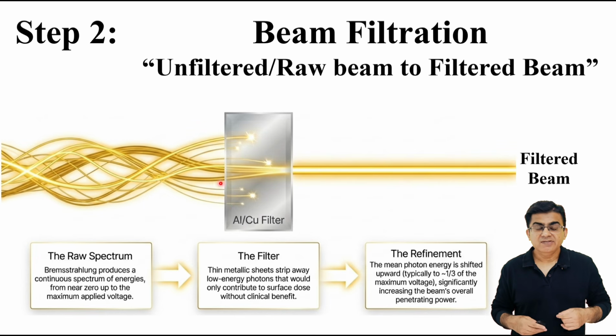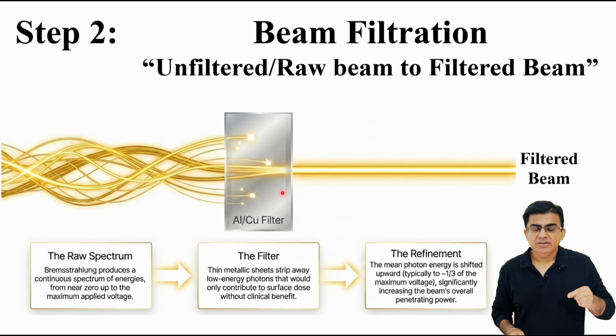It acts as a ruthless physical barrier. It selectively absorbs those dangerous low energy photons. This physical filtration process is called beam hardening. Beam hardening. Remember, examiners will strictly look for the exact textbook terms for this process. Beam hardening. By stripping away the weak photons, the filter shifts the average energy of the beam much higher. The maximum energy stays the same, but the overall average energy increases. This is exactly how we optimize clinical safety and increase the penetrating power of the beam.